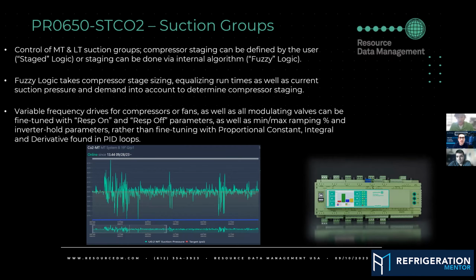Just to get back to response on and response off really quick. In the slide, it says for frequency drives, but that could be for your case controllers, for your electronic valves. Is that correct? So this is not just for the drives. This could be for any specific component that has an opening percentage or up and down ramping.